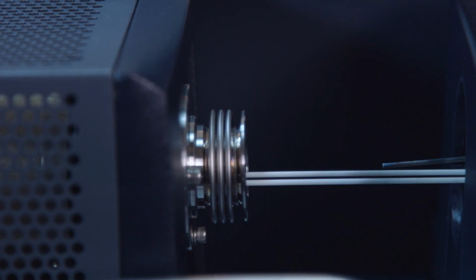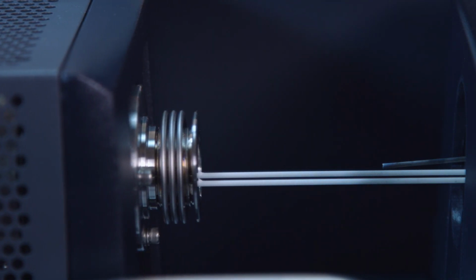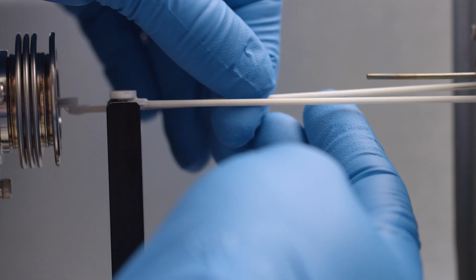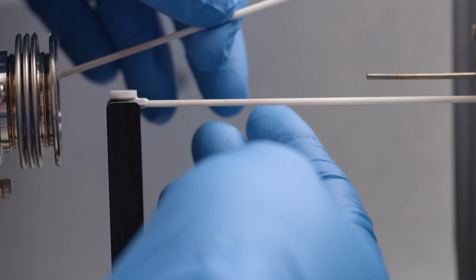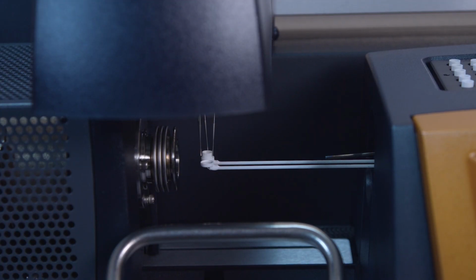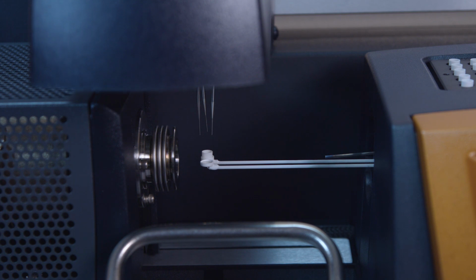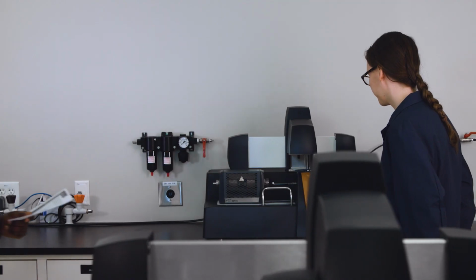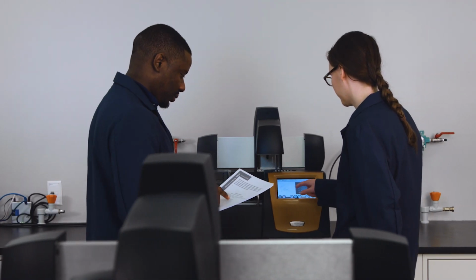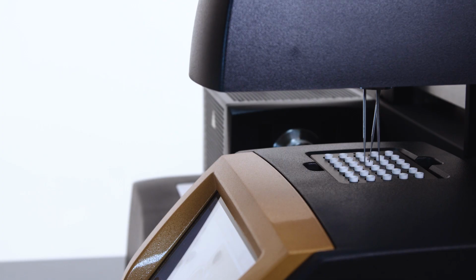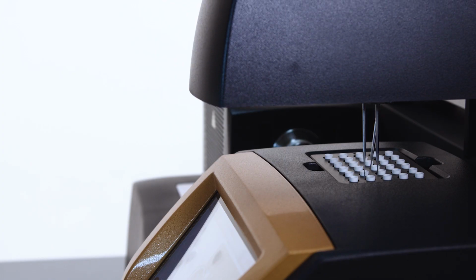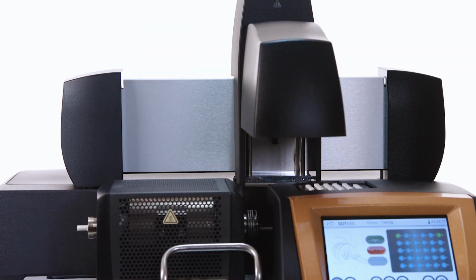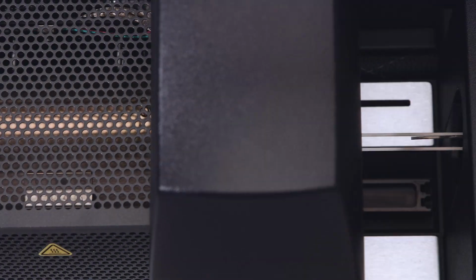Both the thermobalance beams and SDT furnace can be easily replaced by the user. The quick connect beam design and pop-up beam support make beam replacement faster than ever, greatly increasing the uptime of the versatile Discovery SDT. To help optimize productivity, the new Discovery SDT comes with a rugged, linear 30-position autosampler. Tested extensively to ensure reliability, the Discovery SDT autosampler allows for quick, efficient, and repeatable unattended experimentation.